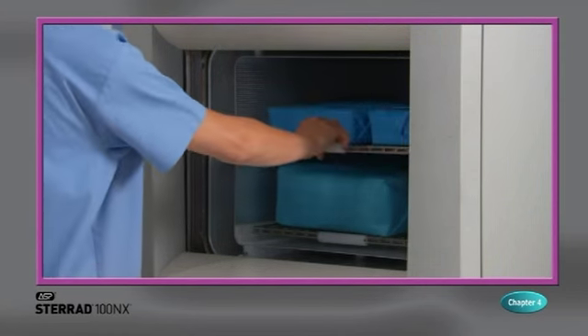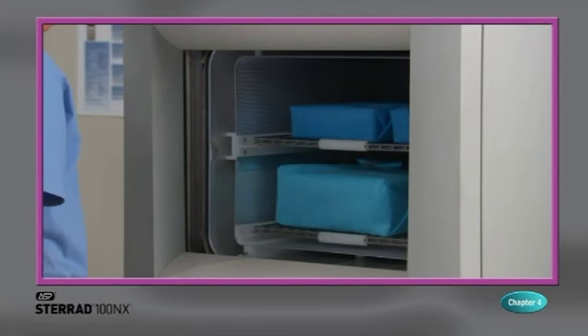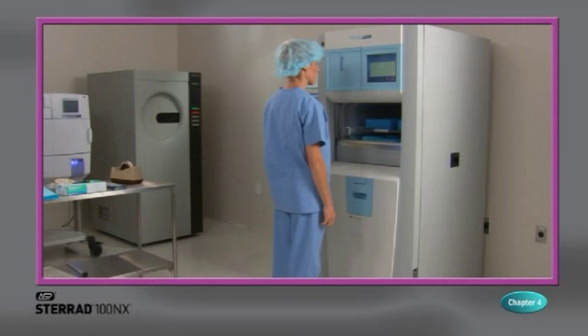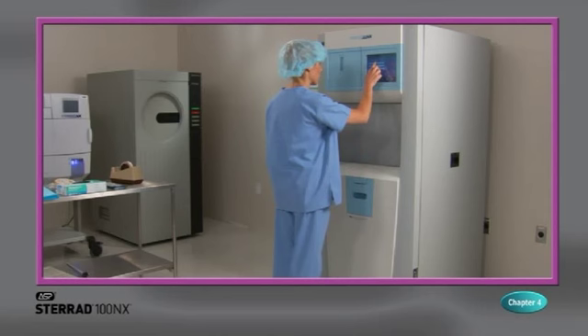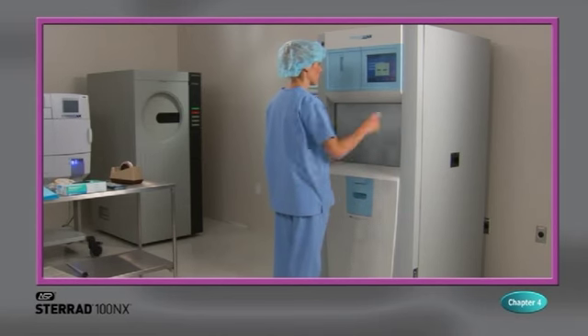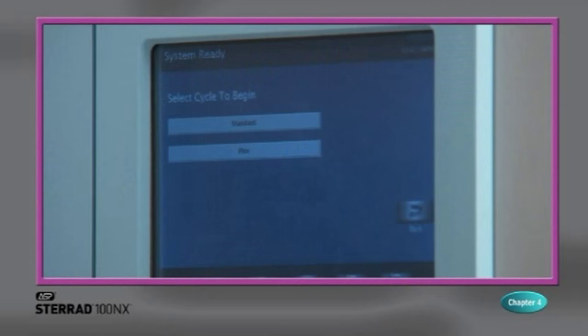When you are finished loading the chamber, close the door by tapping the footpad or pressing the Close Door button on the touch screen. When the load has been placed in the chamber and the door has been closed, use the System Ready screen to select and start a cycle. The System Ready screen displays 2 options, allowing you to select one of the following cycles. Standard cycle sterilizes the load in about 47 minutes. Flex cycle is specifically designed to process 2 flexible endoscopes and sterilizes in about 42 minutes. If your machine is equipped with any additional cycles, they will also appear as buttons on this screen.